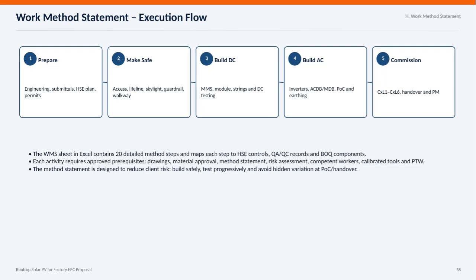Here's an overview of the work method statement execution flow for the rooftop solar PV project. The process begins with the prepare phase, where we handle engineering details, submittals, HSE plans, and all necessary permits. Next, we focus on making the site safe, installing access points, lifelines, guardrails, and walkways to protect everyone involved. After safety is ensured, we move into building the DC side of the system, including mounting modules, creating strings, and conducting DC testing. Following that, we build the AC side, which involves installing inverters, AC distribution boards, points of connection, and proper earthing.